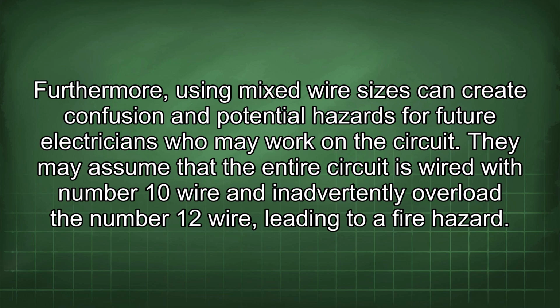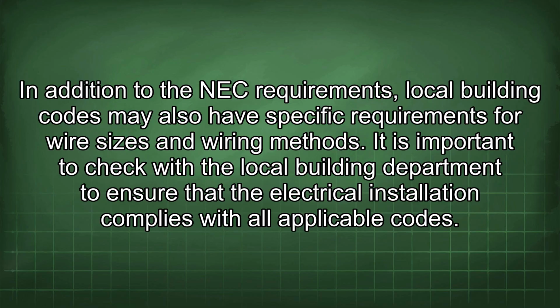Furthermore, using mixed wire sizes can create confusion and potential hazards for future electricians who may work on the circuit. They may assume that the entire circuit is wired with number 10 wire and inadvertently overload the number 12 wire, leading to a fire hazard. In addition to the NEC requirements, local building codes may also have specific requirements for wire sizes and wiring methods.